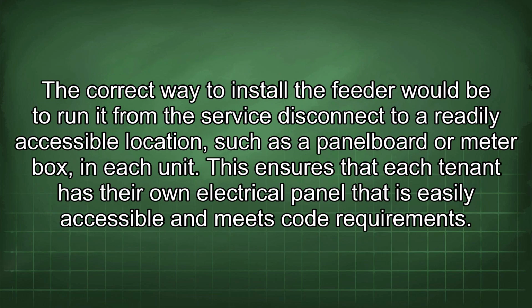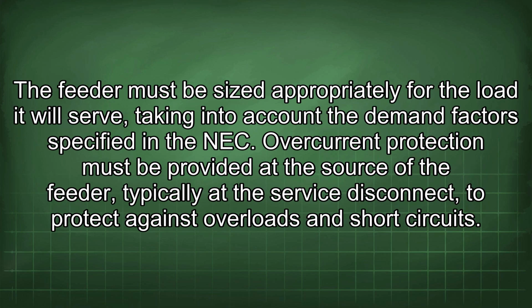The correct way to install the feeder would be to run it from the service disconnect to a readily accessible location, such as a panel board or meter box, in each unit. This ensures that each tenant has their own electrical panel that is easily accessible and meets code requirements. The feeder must be sized appropriately for the load it will serve, taking into account the demand factors specified in the NEC. Overcurrent protection must be provided at the source of the feeder, typically at the service disconnect, to protect against overloads and short circuits.